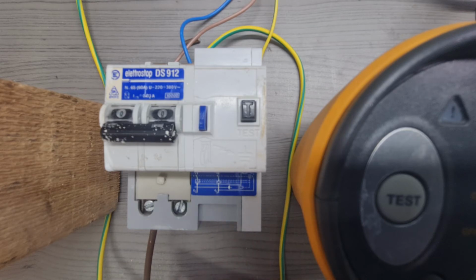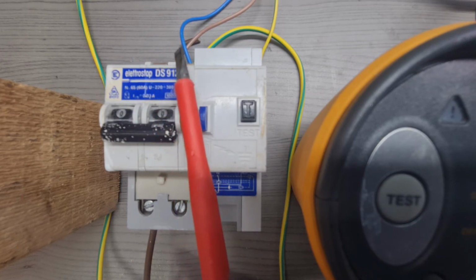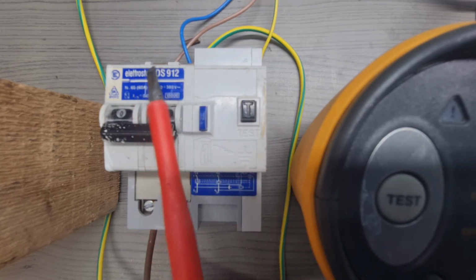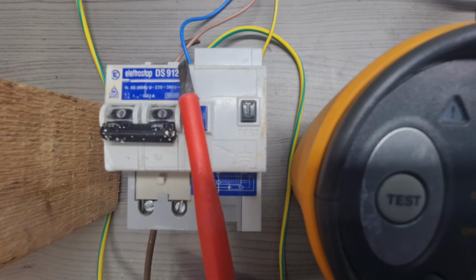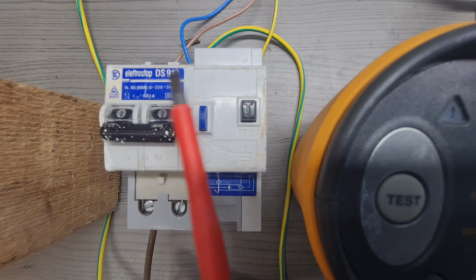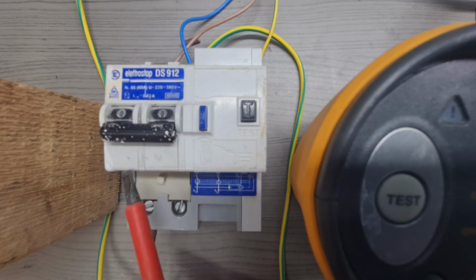Obviously I have to trick the RCD into generating a fault without switching off all of my workshop, and therefore I have one wire connected at the output side on the line conductor, and on my input I have connected an earth wire which is connected to the neutral of my input side, so that the imbalance is only across this device, and therefore I do not have a tripping of the main RCD.